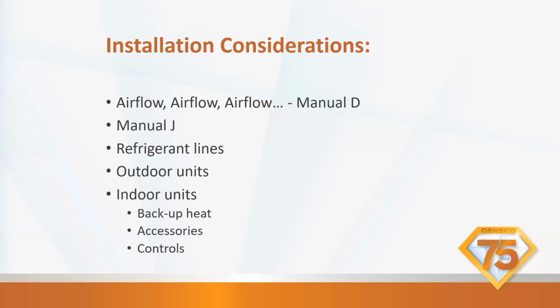Installation considerations, what we're going to talk about today, basically. Airflow. That's the number one reason that air conditioning and heat pumps don't work. Most of the calls that we get center around airflow, and a lot of people don't think that because it has a pressure issue, a charge issue. It's throwing some kind of codes, and it's almost always airflow before you can charge to get the charge correct. So you have to do your airflow first and then the charge.